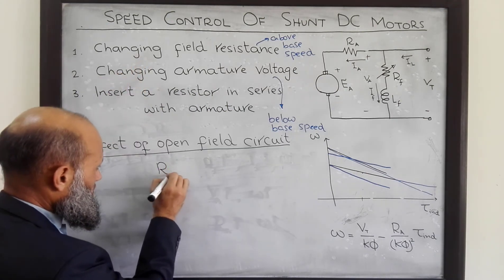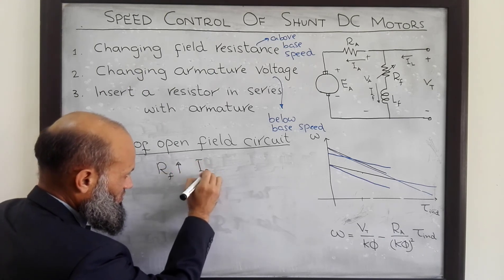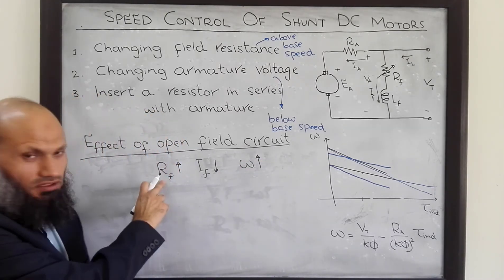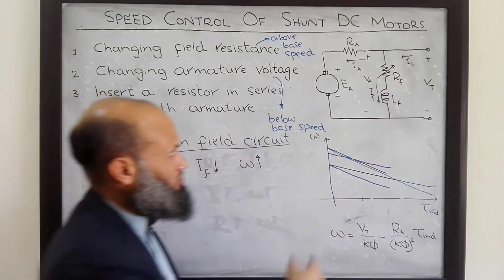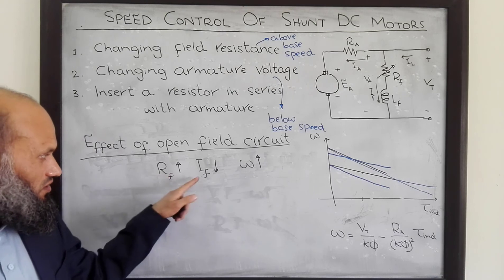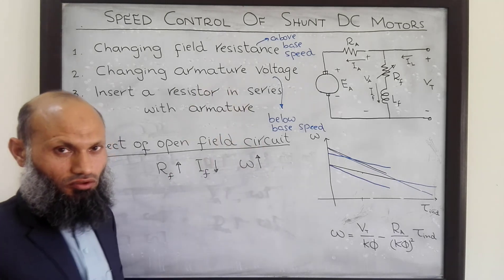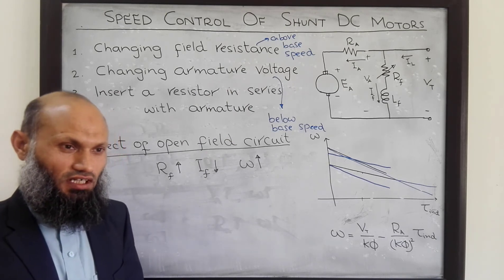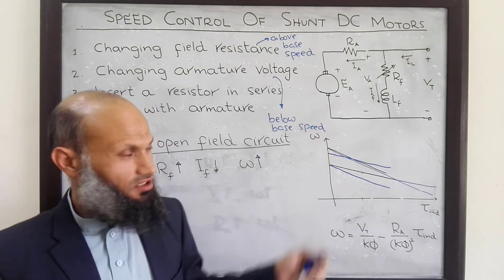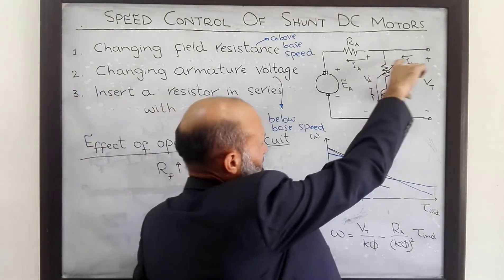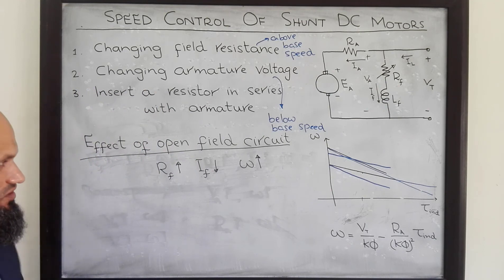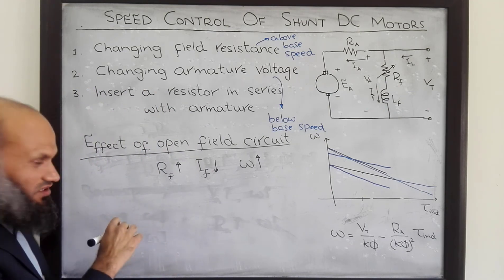Increasing RF results in a decrease in field current and thereby an increase in speed. If the field circuit is opened — that is, the connection is lost — then RF approaches infinity, field current approaches zero, and speed approaches infinity. Practically, the motor will gain very high speed and therefore be damaged mechanically. Therefore in larger DC motors there is always an arrangement to disconnect the motor from the power supply when the field circuit gets opened. We shall discuss that arrangement when talking about starter circuits for DC motors.